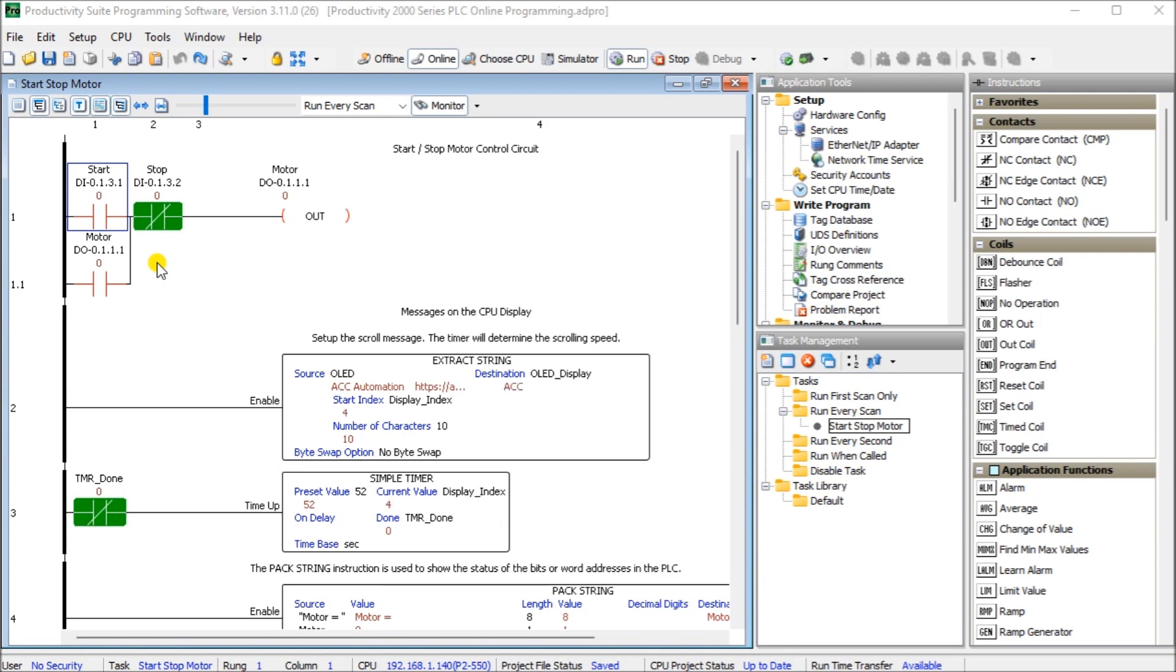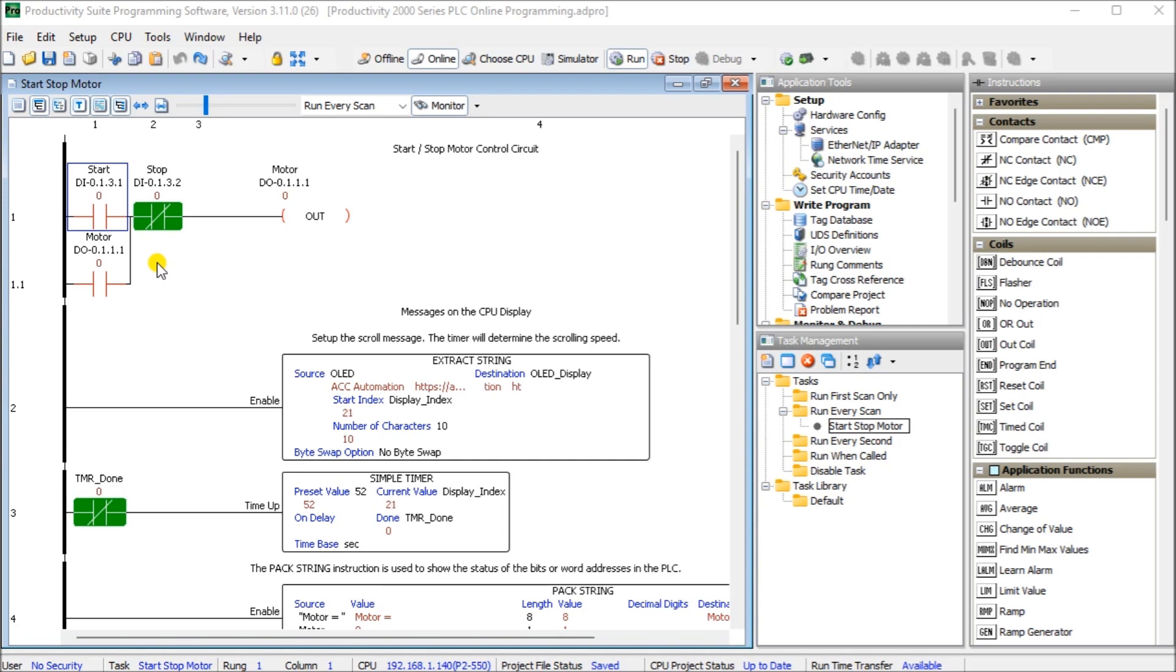We change the ladder logic code and when we save it to the PLC, the current scan of the PLC is held until the new code is written into the unit. It then releases a scan and the new program starts to execute. This happens in milliseconds so our process can continue to operate. We will be taking our existing start-stop circuit from last time and add a JOG input using Online Programming.